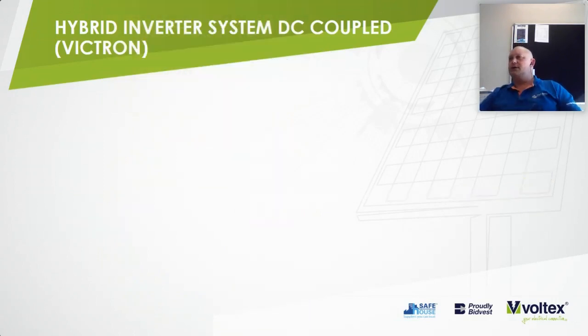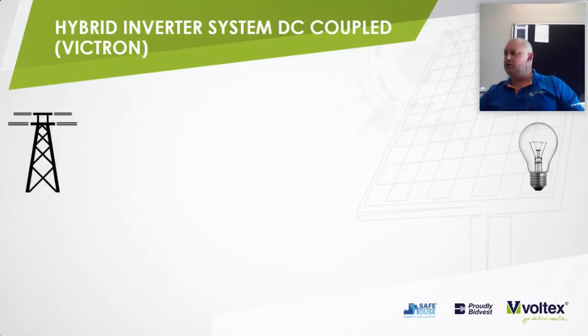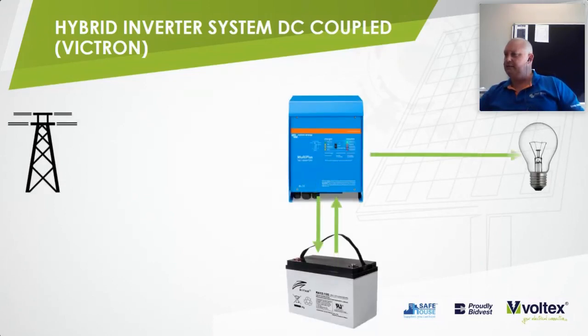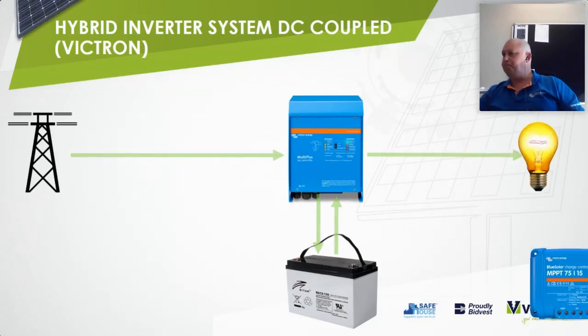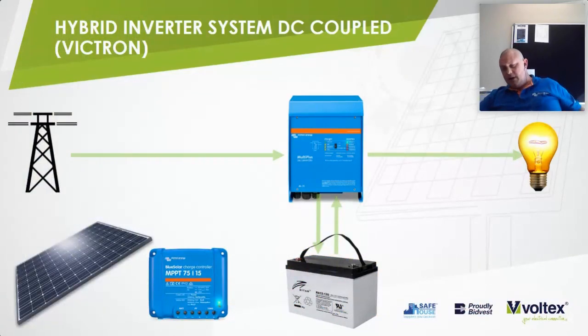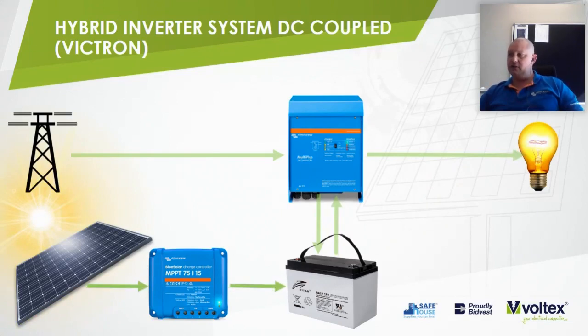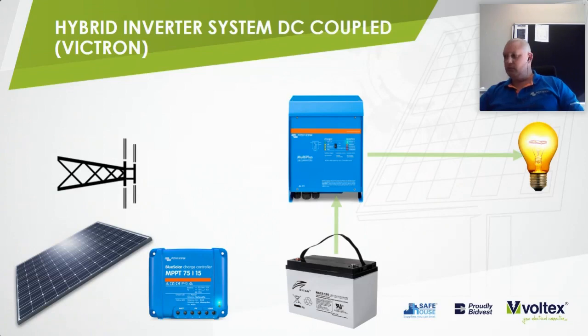Going to our next system, it's also a DC coupled system, but this is with a different brand of equipment, also a higher end brand. So similar to the rest, you've got your loads, you've got your utility, nice shiny blue inverter. With this inverter, it is not a hybrid inverter. This is a bidirectional inverter, also known as a battery inverter or an inverter charger. By adding a solar MPPT charge controller to it, you can charge batteries directly and surplus power can be fed to the loads. In the event of Eskom failure, once again, reverting to batteries, the inverter will change the DC power into AC power, keeping your loads covered.